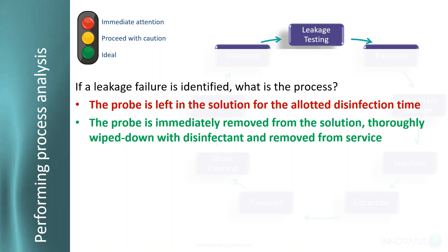So if a leakage is identified, what is the process? As I mentioned earlier, get it out of there. If we have a failure, the little red light goes on, or if you're using a quantifiable leakage tester and the leakage is above the preset safety level, remove the probe from service immediately, wipe it down, and ship it off to us, and we'll get it taken care of for substantially less than a catastrophically damaged probe.